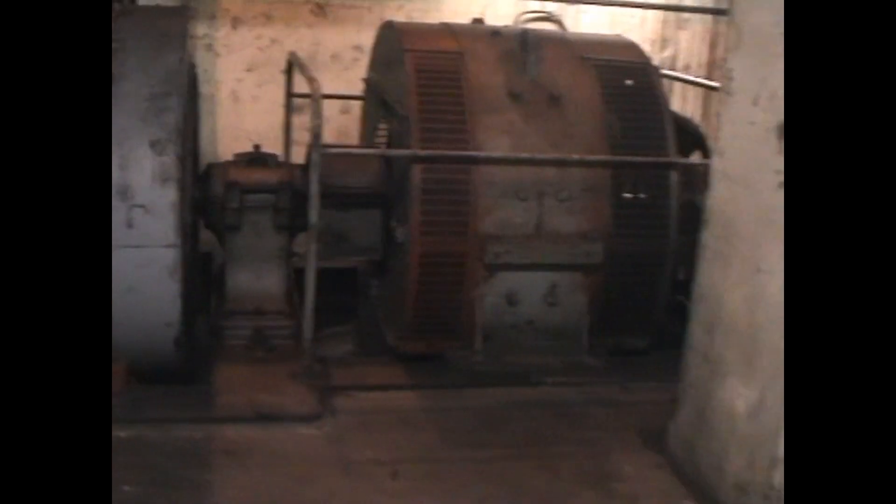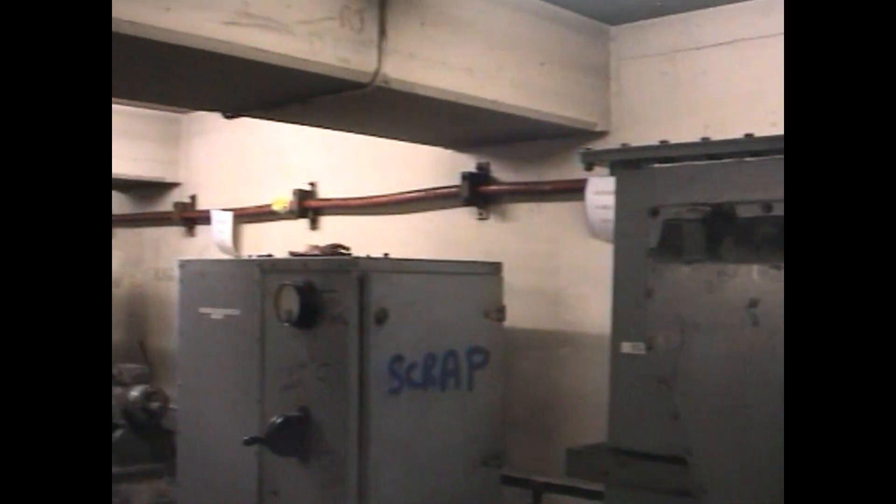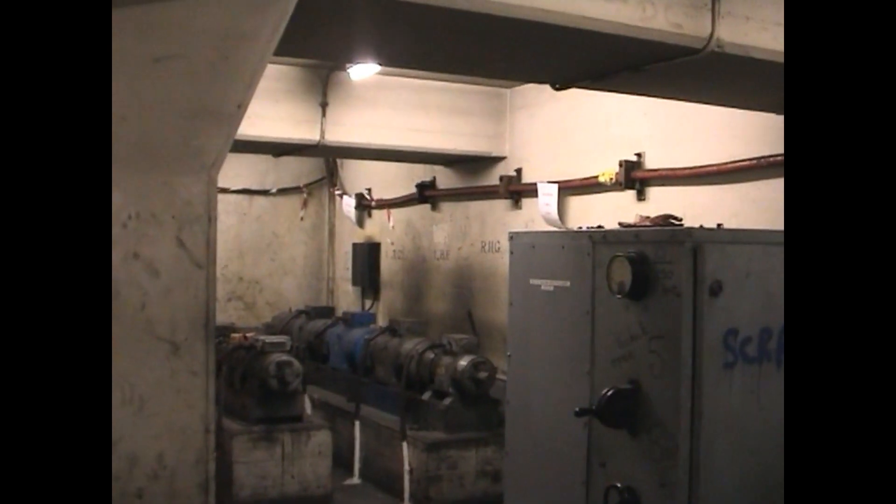Reactor, starting reactor. We've got this coming out. We're going to have to throw a hole in the ceiling. We've got a live cable running along the back wall here. 6.6kV cable — we're going to be careful. We've marked all the cables which are live.